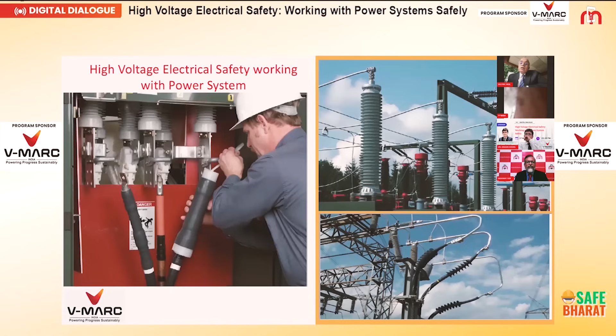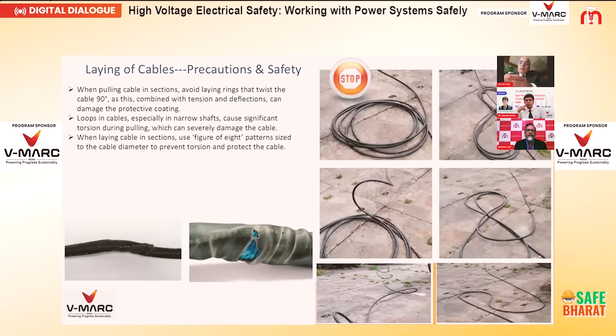Now, when you are opening the cable, even the small cable, when you are putting it in a round shape, better put it in an 8 shape. This is a very common phenomenon in the cable line. In case you are not using the 8 shape, the problem will be, as shown in the left side of this picture, where it gets twisted and spoils, and failure of the outer sheath will occur.